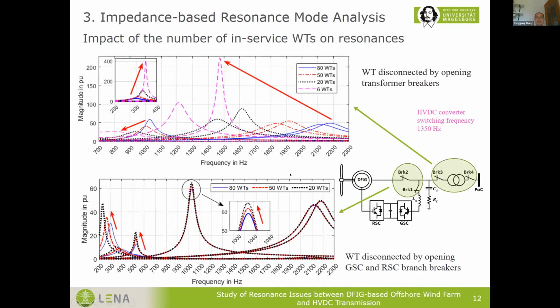Then as for disconnecting individual wind turbines from grid, which can be realized by disconnecting the transformer breakers or the turbine branch breakers, these two cases are presented here separately. For different scenarios, for opening the transformer breaker cases, two resonance peaks can be observed at around 350 Hertz and 1450 Hertz, which tend to amplify the typical 7th harmonic and the HVDC converter switching frequency. For opening the turbine branch breakers, the variation of in-service wind turbines have mainly impact on this resonance modes.